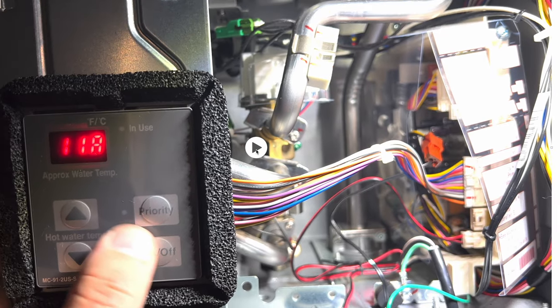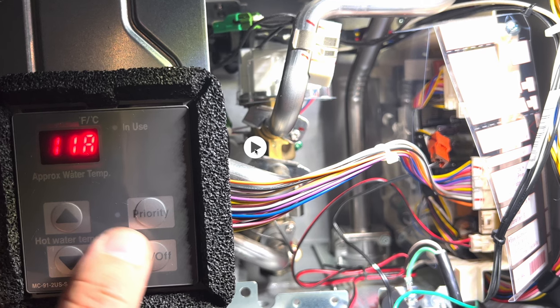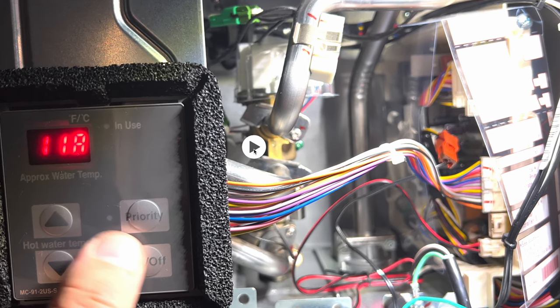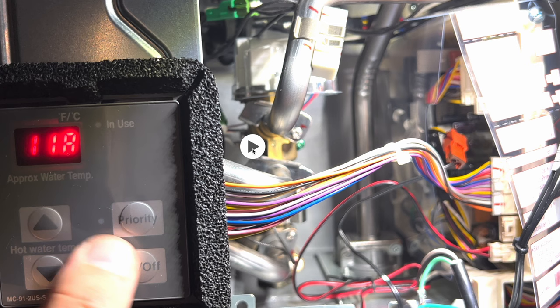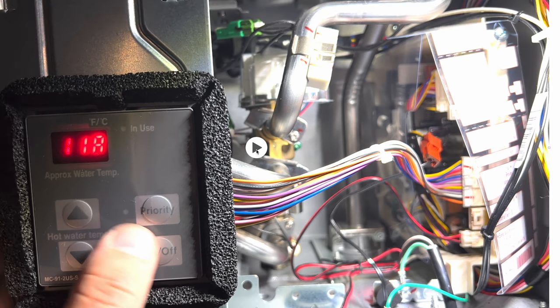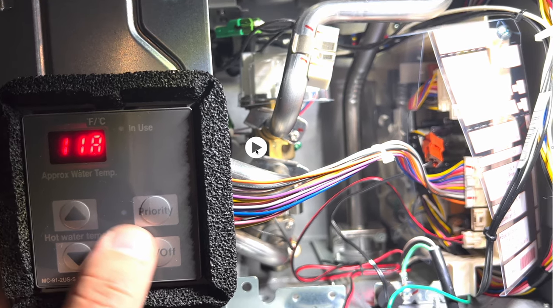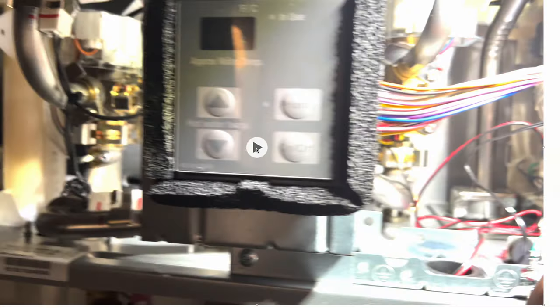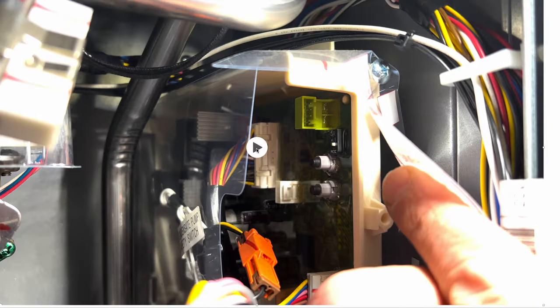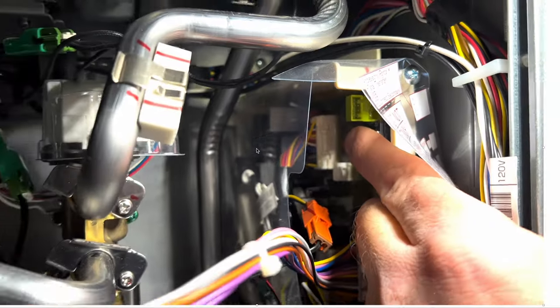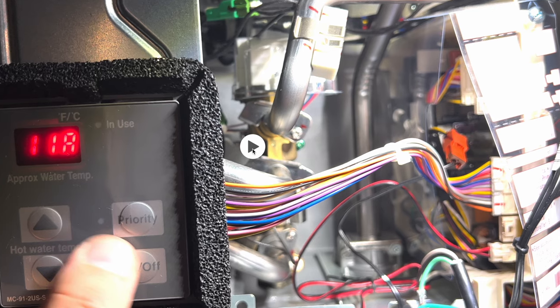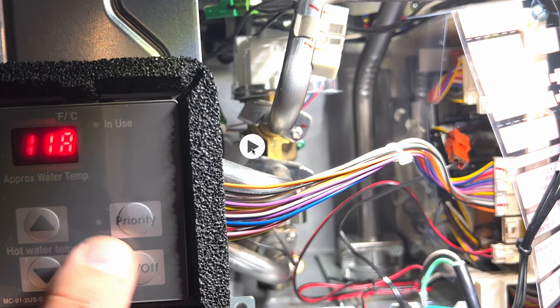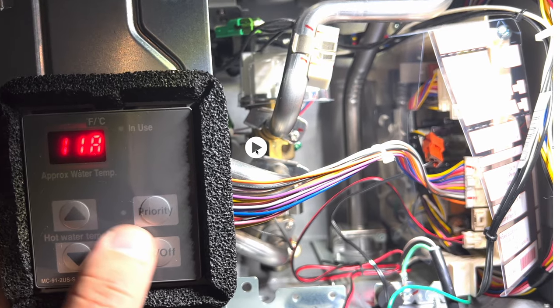Setting 11 is for maximum flow rate. The default selection A is for standard flow and B for maximum flow. Selecting B will give you more water flow. This is the last setting you can make. Once you are done with the settings, to exit the menu, go back to the motherboard and push and hold the A button until the screen goes blank, then push the on button to turn the unit back on. Congratulations, your water heater has been reprogrammed.